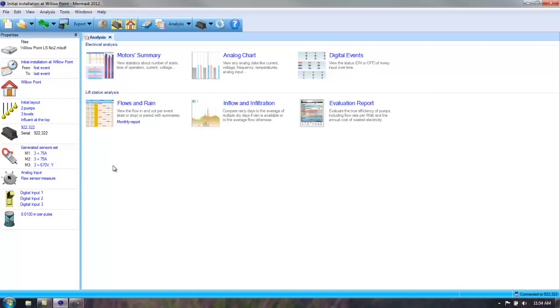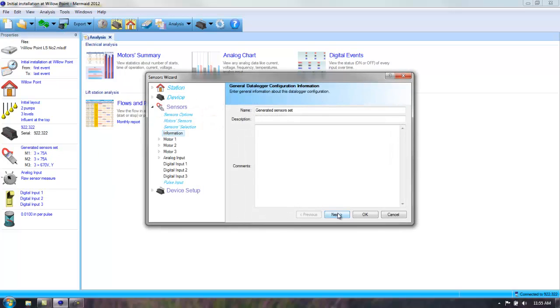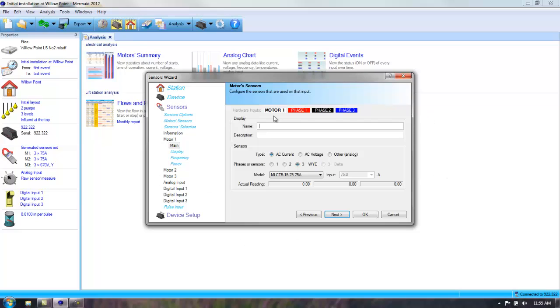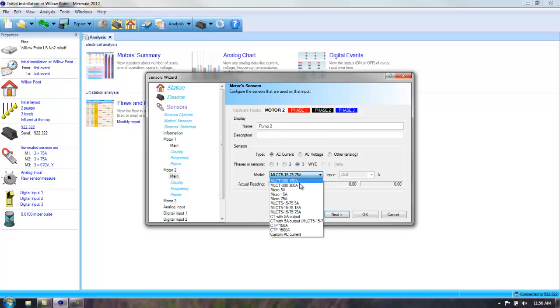Now we also said that the sensors were incorrect. We had set it up for 75 amp sensors. To change this, just go into the generated sensor set, and you'll go to each individual sensor. Now, typically, the name of that would be motor 1 in any of your reports, but I'm going to say it's pump 1. And pump 1 was an AC current unit, but instead of 75 amp, I'm going to be using the 300 amp clamps. So I just selected that and hit next. Now for motor 2, I'm going to call it pump 2. And I'm going to reselect the model of clamps to the 300 amp clamps. And then that is all I'm going to do.